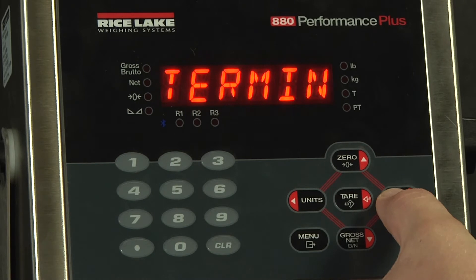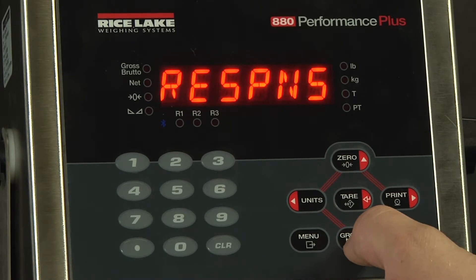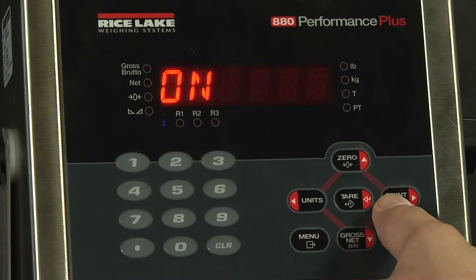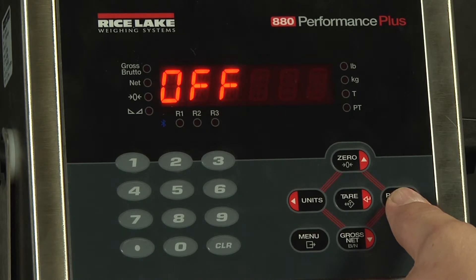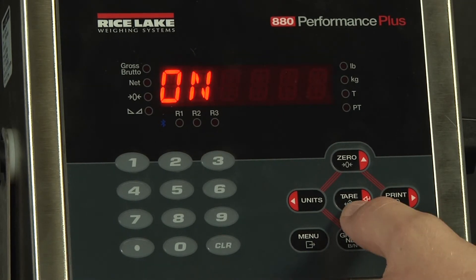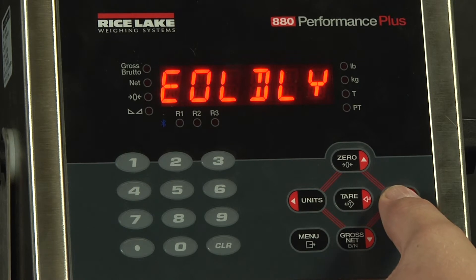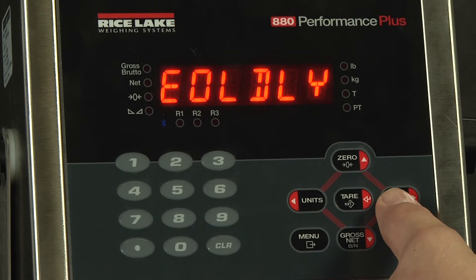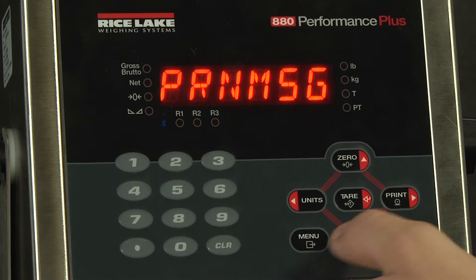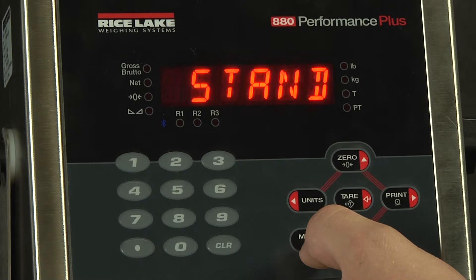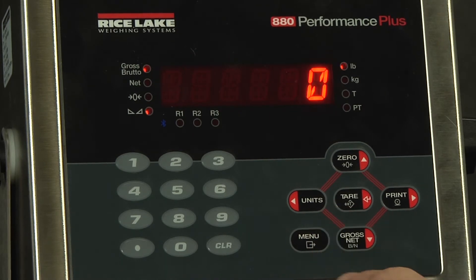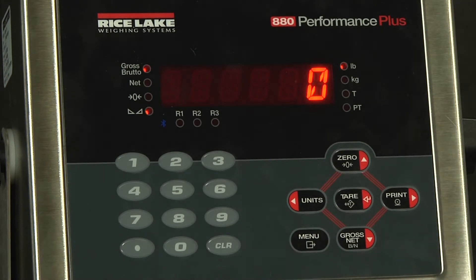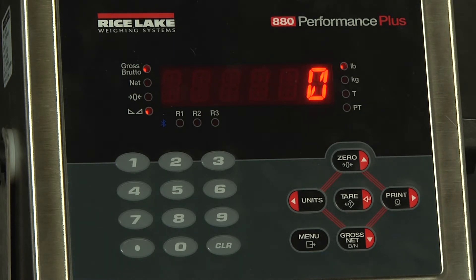At this point we will scroll over and verify that response is also on. With response off, we would not get anything back after sending a command. However, since it is on, we know that we should be getting something back. At this point we can hit the menu to save and exit. Now that we've verified that all our communications parameters are set, we want to verify our actual physical setup.